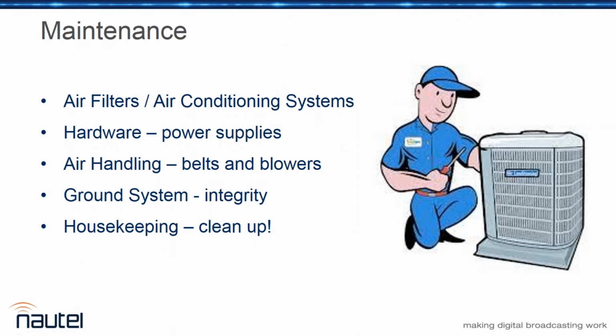Let me say one thing about backup generators in particular: if you don't go out and actually simulate an honest-to-God utility failure, you have no idea what's going to happen when that occurs. Just relying on the generator's weekly exerciser to say 'I checked the box, it works' - no, you didn't. Go out there at a time of your choosing when it won't be a disaster if things don't go right, pull the main breaker, and just watch and see what happens.